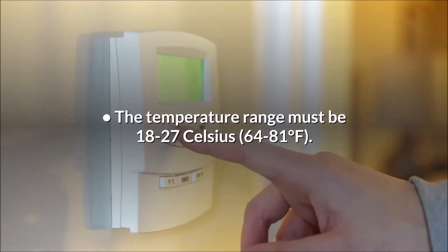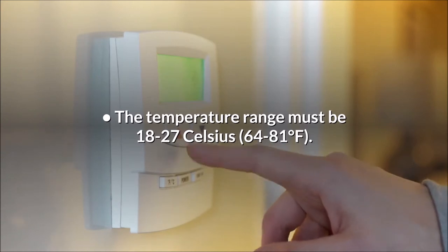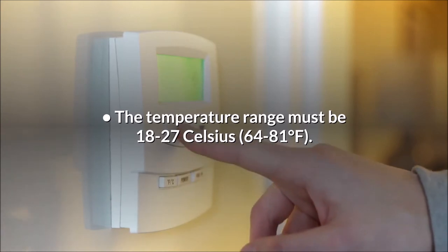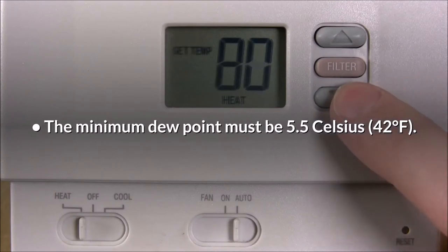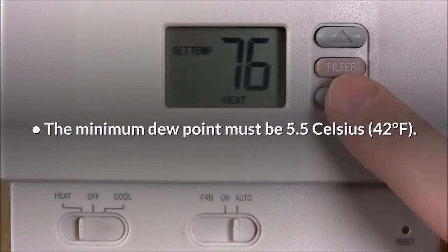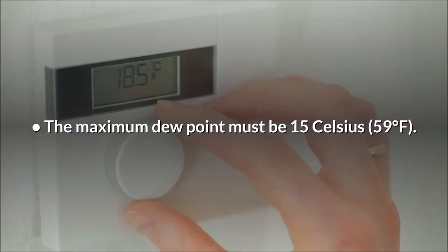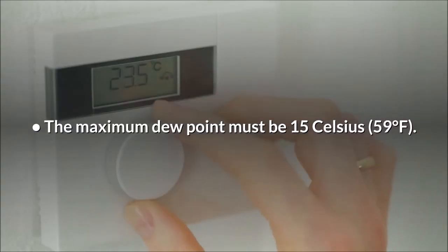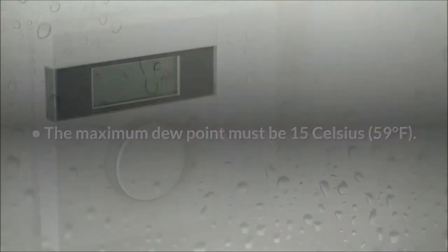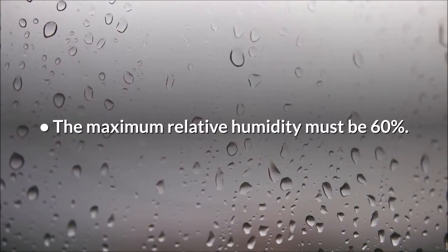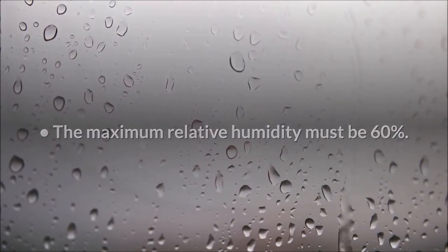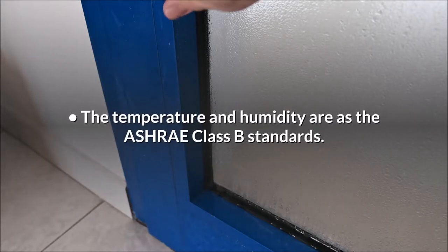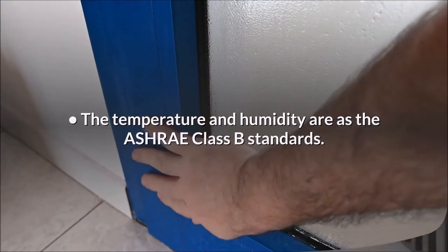The temperature range must be 18 to 27 Celsius, 64 to 81 degrees Fahrenheit. The minimum dew point must be 5.5 Celsius, 42 degrees Fahrenheit. The maximum dew point must be 15 Celsius, 59 degrees Fahrenheit. The maximum relative humidity must be 60%. The temperature and humidity are as the ASHRAE Class B standards.